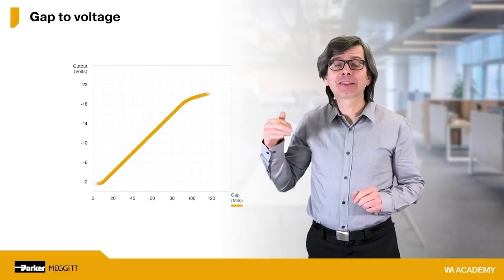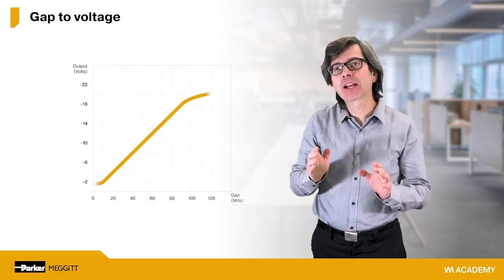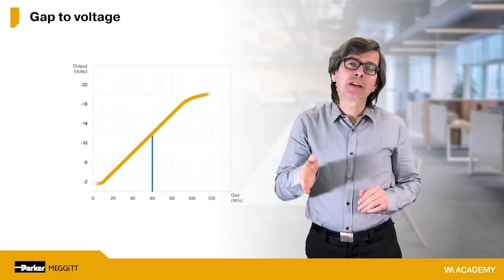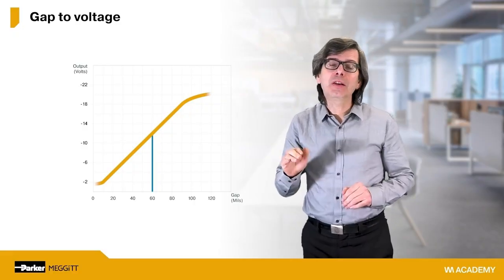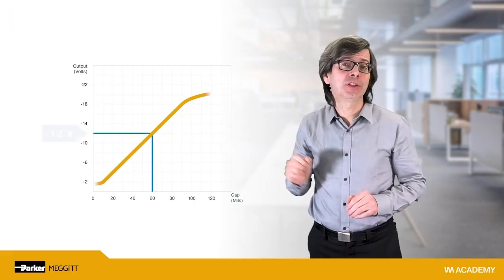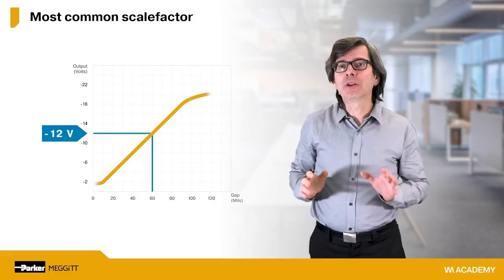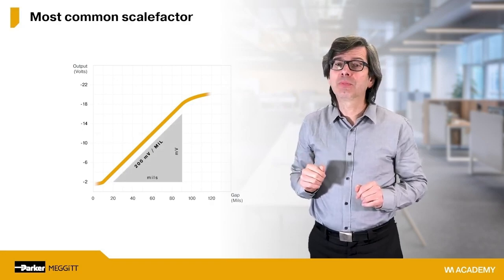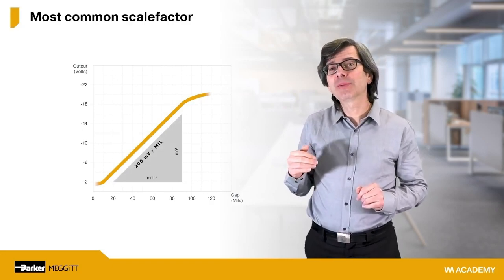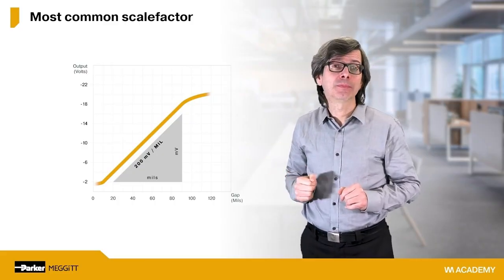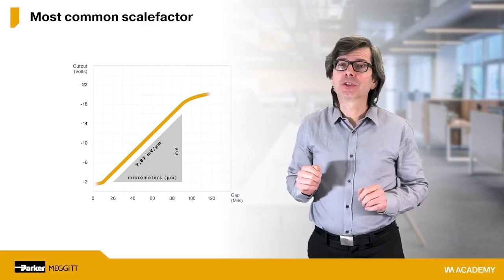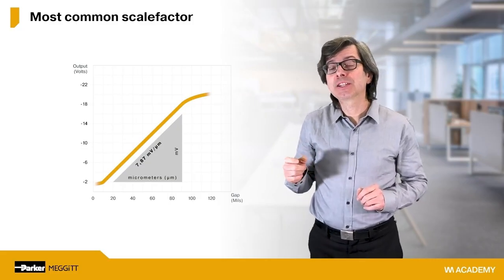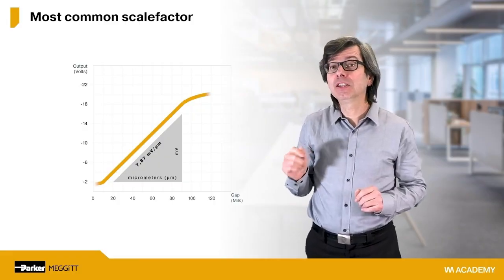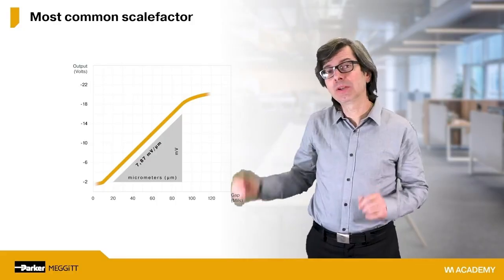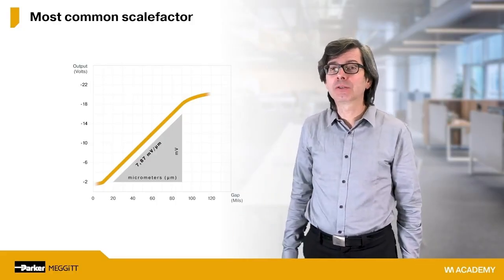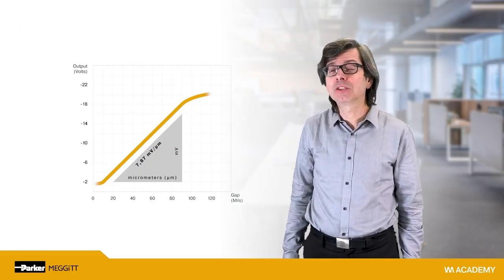If we want to convert gap to voltage, we simply select a particular gap, then extend vertically until we hit the yellow line, and then proceed horizontally to the corresponding voltage. The most common scale factor is 200 millivolt per mil. This is equivalent to 7.87 millivolt per micrometer. However, when doing computations in your head, and for the examples in this lesson, 200 millivolt per mil is easier to work with than 7.87 millivolt per micrometer. And this is the only reason we have chosen to use imperial units instead of metric units.